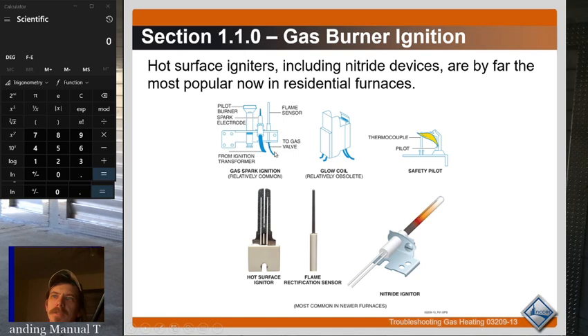So that is actually probably the safest way to prove ignition. It's better than a hot surface igniter, but it's not so much of a difference that anybody really cares. But having a flame to light the gas is always the most guaranteed way to light the gas. So really the best way is kind of intermittent spark ignition, but it's more complicated than a hot surface igniter, so we usually use hot surface igniters.